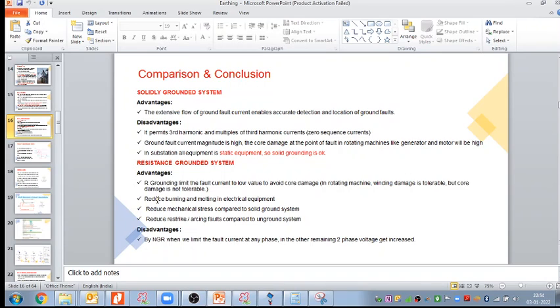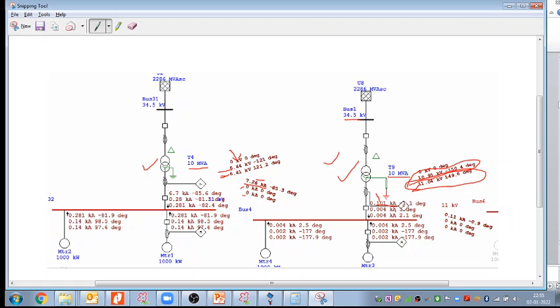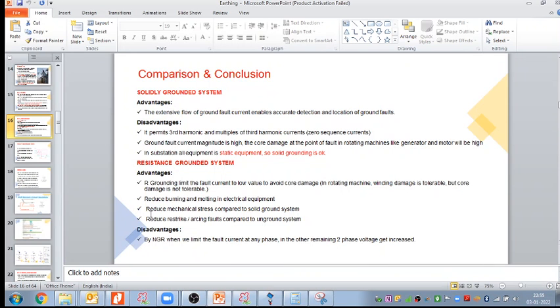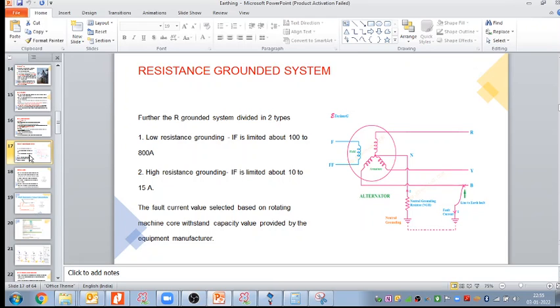Next advantage, it reduces the burning and melting in electrical equipment. Next advantage, it reduces the mechanical stress compared to the solid grounding system. It reduces the restrike or arcing fault compared to the ungrounded system, the ungrounded system, not the solid grounding system. But the disadvantage of NGR is that when we limit the fault current at any phase, the voltage of the other two healthy phases gets increased. That we have seen here. So that is the disadvantage of the NGR. Okay, so now this NGR is again divided into two parts.